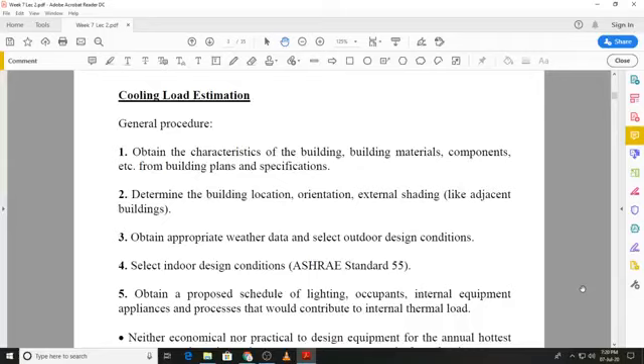When we say orientation, it is, if I look at the north direction, with reference to the north direction, what is the orientation of the building. That will also be required when you will see that when we calculate the cooling loads. We might also be interested in external shading. For example, if that building has tall structures or tall buildings close by, that will also affect the cooling load.